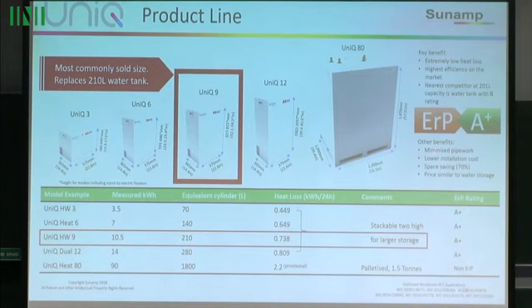Okay, well luckily I have a slide on that as well. This is according to the ERP, Energy Related Products Directive, running their standard test, which essentially gives you the 24-hour heat loss. So if I take a UniQ HW9, equivalent to a standard 210 litre cylinder, it loses 0.738 kilowatt hours per 24 hours through the walls.